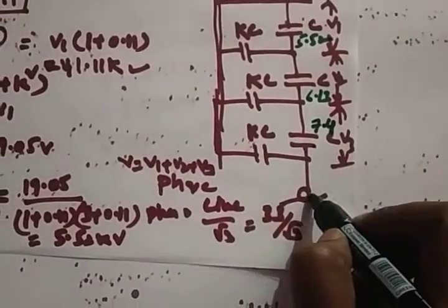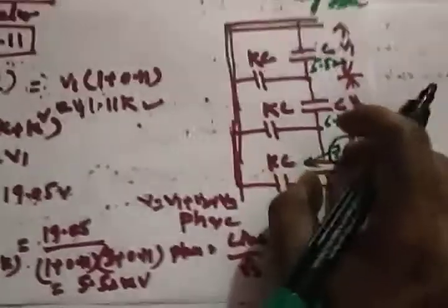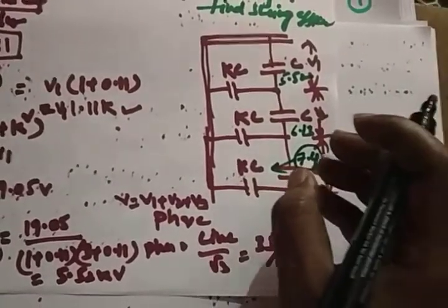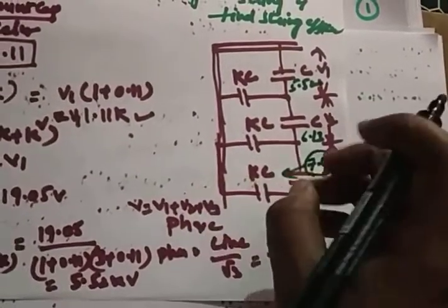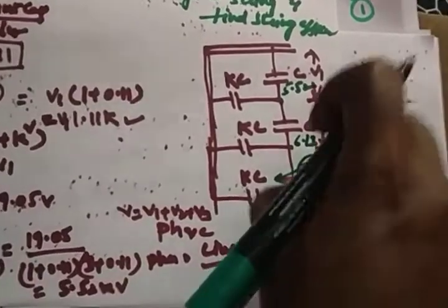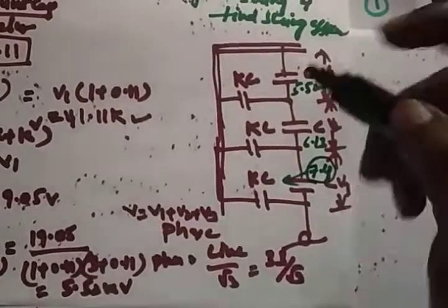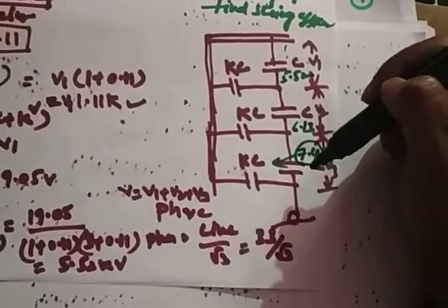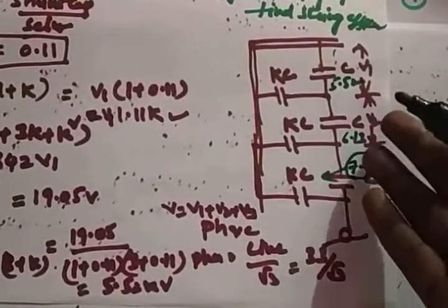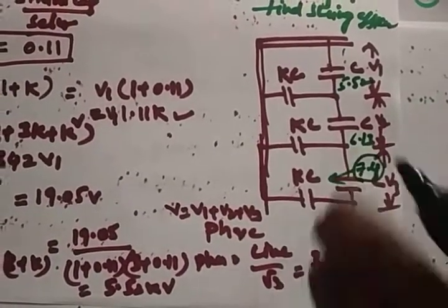disc which is nearer to the conductor has the maximum stress, right, the maximum voltage. So definitely there will be a first chance for a flashover or a puncture on this disc. If this disc fails, definitely the total string will get damaged. So that's why we need to maintain a constant voltage across each and every disc. From this you will see the voltages are non-uniform, right? The voltage across the disc nearer the conductor is very high.